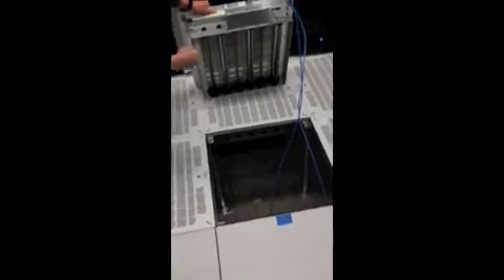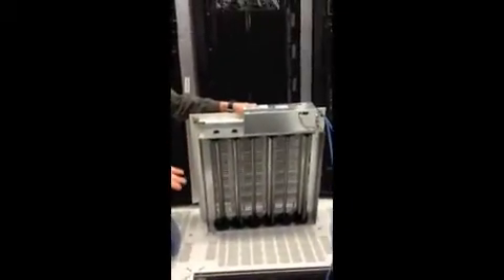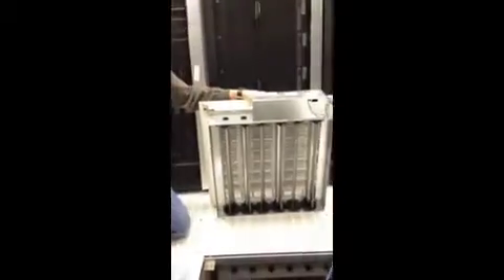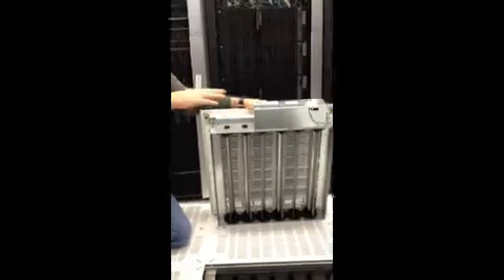So these have louvers on the bottom that are controlled by a slow-speed motor in here, and it takes about 100 seconds for it to go from all the way open to all the way closed, or vice versa, and they can all be operated simultaneously. So within 2 minutes, I can open or close every AVT in this data center. You'll note high-density power areas like this, we have one AVT in front of every rack so that we can control it. In lower density areas, we alternate them with ordinary, roughly 30% vent tiles so that you can just modulate slightly.